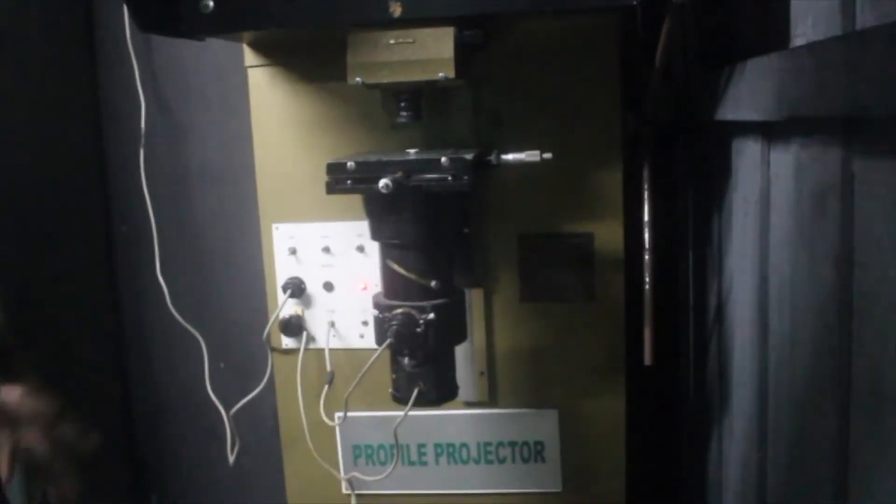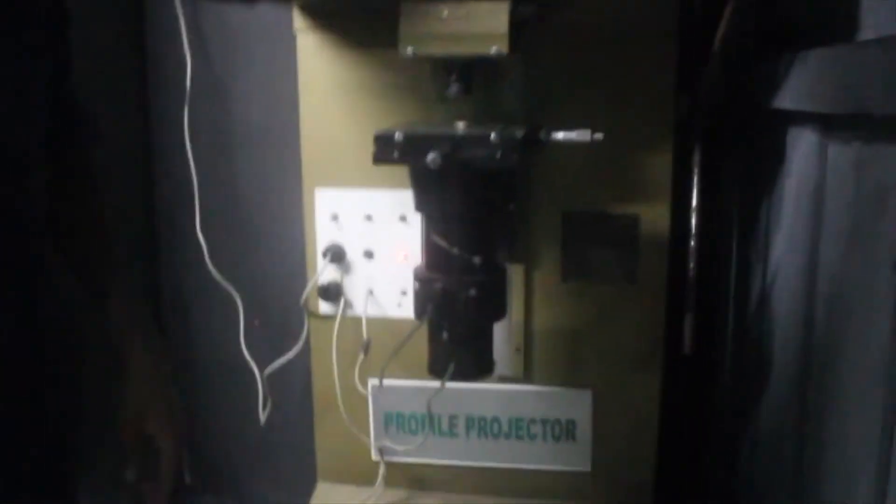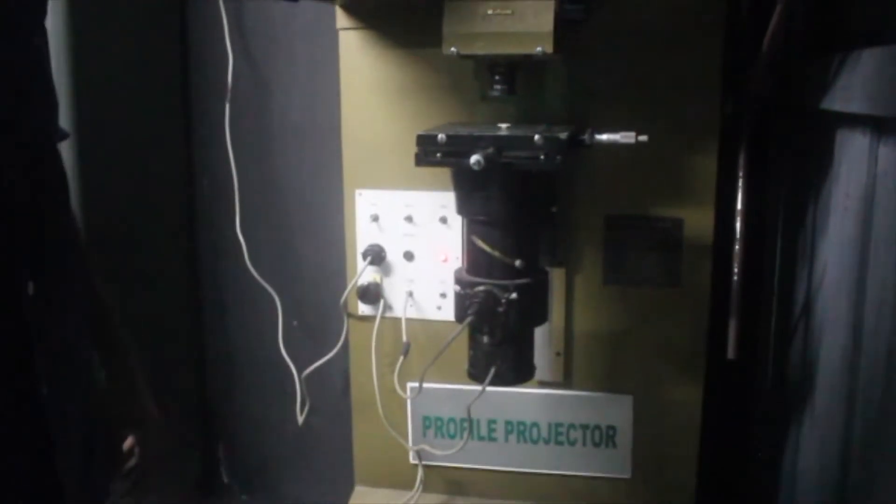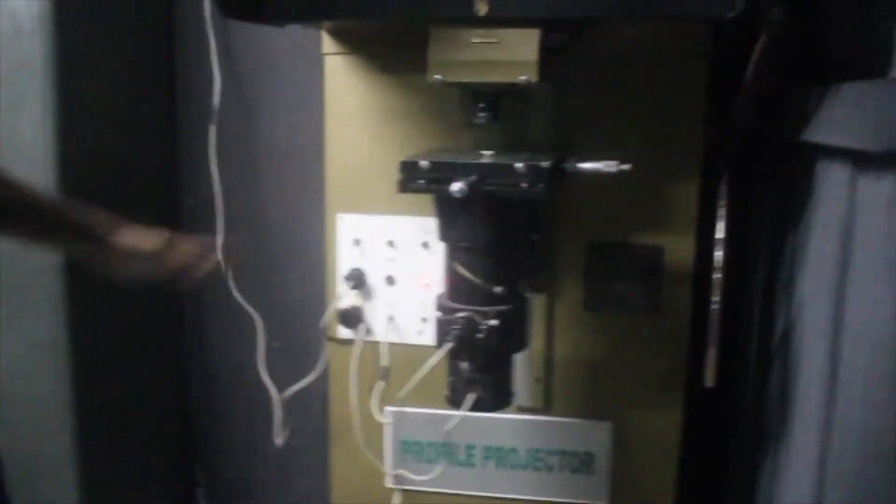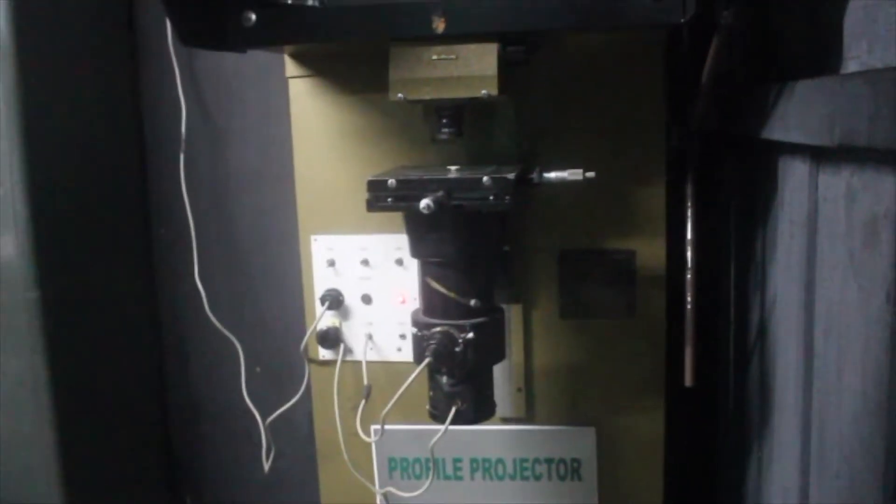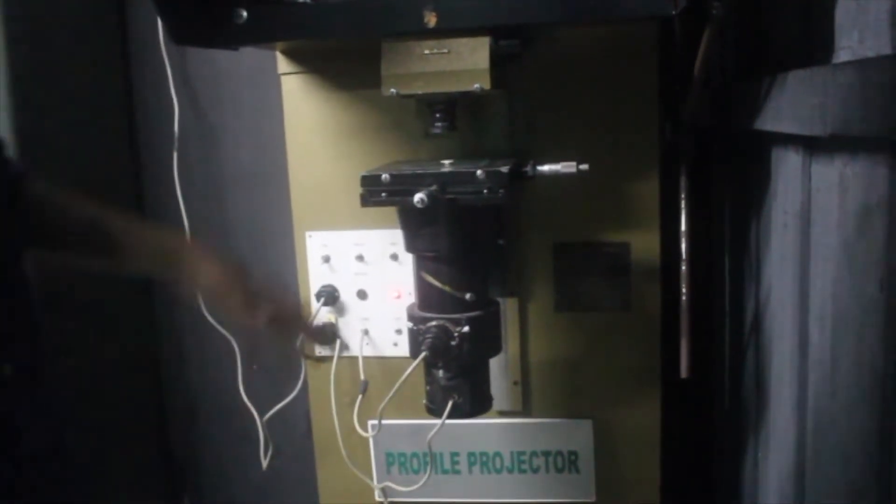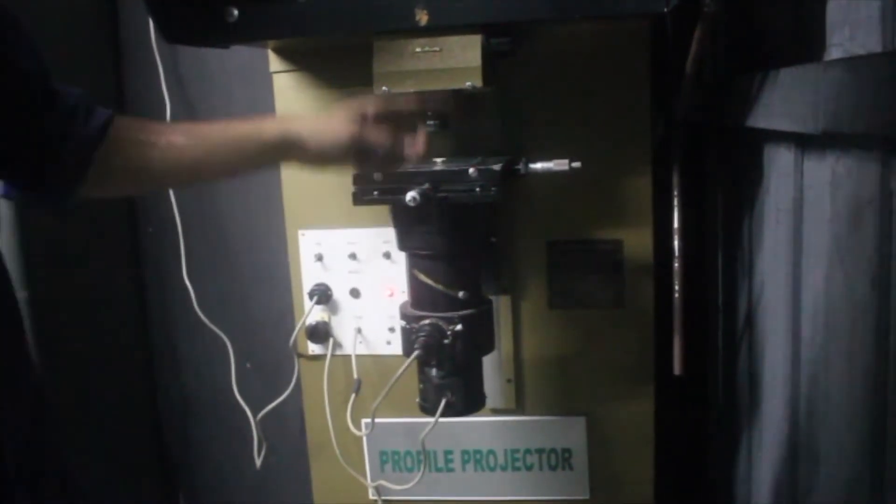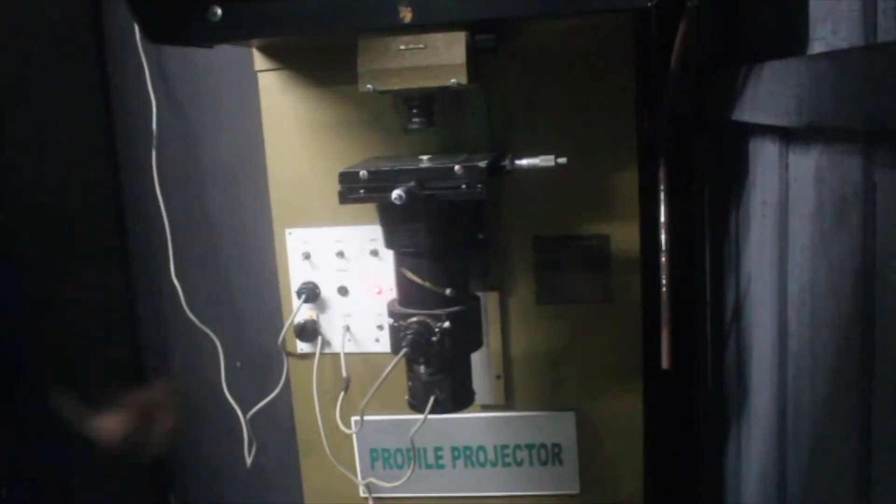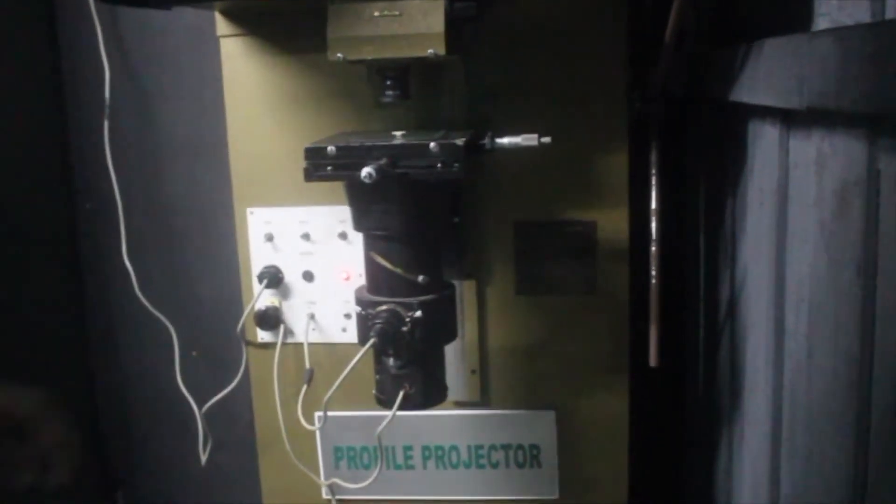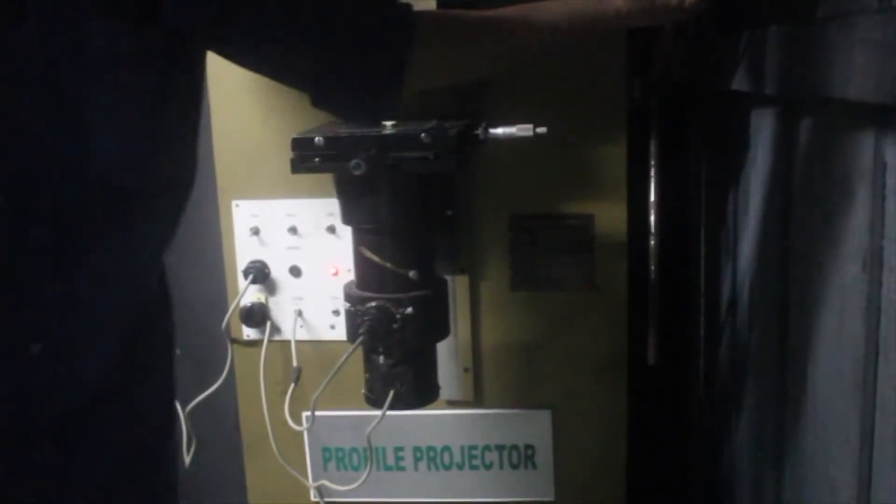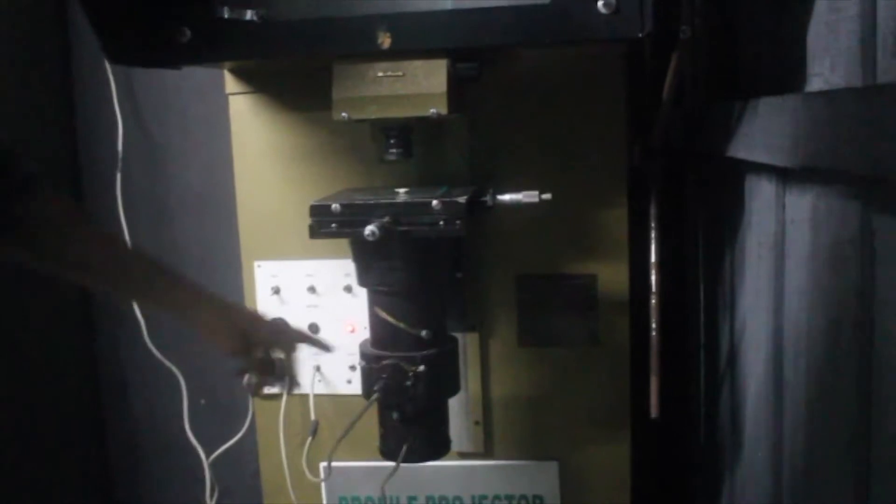These are the basic parts of a profile projector. Now we have some other parts for focusing. This is the wheel used for focusing, and here this is used for fine adjustment.